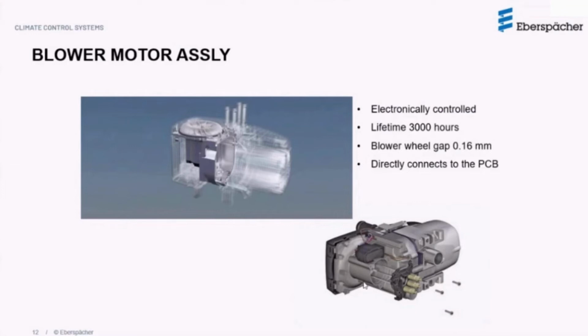There are certain protocols to be followed when you open, close, or tear down and reassemble a heater, which allow the IP protection classes to be maintained. One recommendation is that the cover that sits on the blower needs to be replaced every time you separate the two parts. It's not that it gets damaged — there's no visual indication of damage when you separate the two — but the seal is compromised. So we always recommend that this cover be replaced.